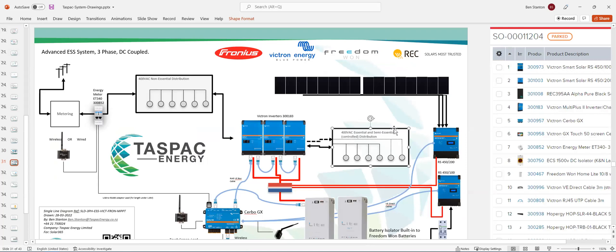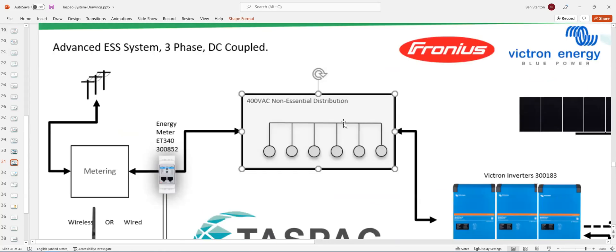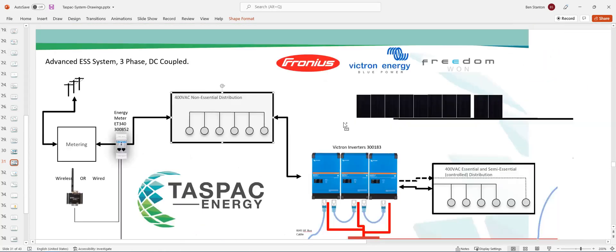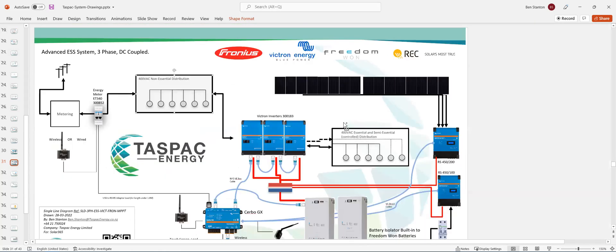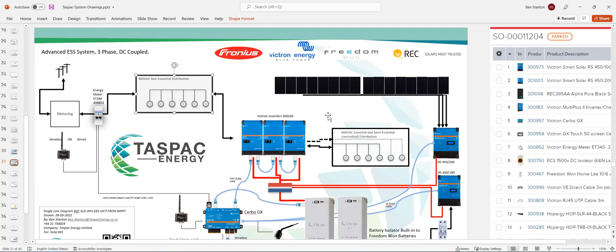Now, you may decide if there's huge loads on the system, like say a spa pool or a swimming pool or heat pumps, you may decide to put those on the non-essential, which basically means non-essential is if the grid goes down and you're running just from the inverters, then non-essential will not be alive.